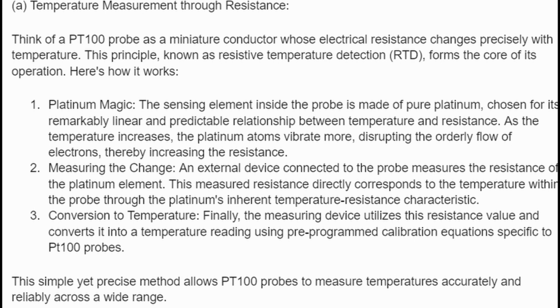The sensing element inside the probe is made of pure platinum, chosen for its remarkably linear and predictable relationship between temperature and resistance. As the temperature increases, the platinum atoms vibrate more, disrupting the orderly flow of electrons, thereby increasing the resistance. 2. Measuring the change.